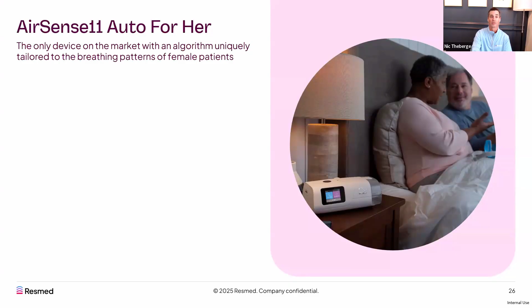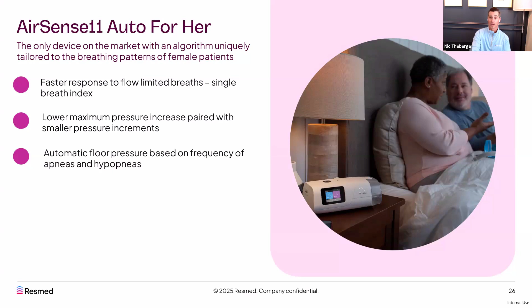The standard auto will have a 3-breath moving index and will respond breath by breath, but the For Her mode will respond and look at 1 breath right away. There's a lower maximum pressure, right? It's paired with smaller pressure increments. So responding faster, but with smaller pressure increments. There's also a floor pressure that's based on the frequency of apneas and hypopneas. Again, that's specific to women. And the algorithm prioritizes the response to partial collapses and snore events above 12 centimeters of water. I know those seem like, how does that work? But ultimately, they all work together to provide a lower average pressure with the same amount of treatment.